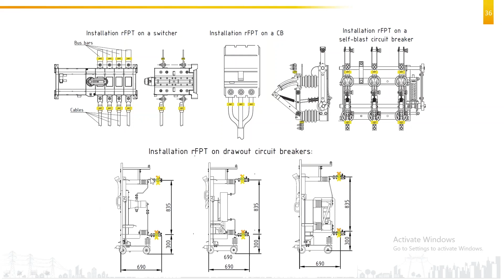So this particular example is taken over 4 cabinets. In the 4 cabinets there is one bus bar cabinet and there are 3 chambers. We will install RFPT on the incomer and outgoing of the circuit breaker, and at all the joints in the bus bar chamber. We will install sensors in each cabinet, in circuit breaker 1, circuit breaker 2, and the bus bar chamber. And then we will have one common FPA which will monitor all 4 cabinets.